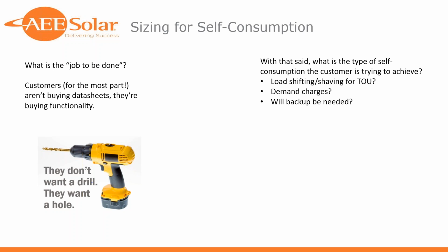And the last thing I threw in here, it's not a specific application on its own, but typically when we're talking about these solutions for residential customers, you've got to think, is backup going to be needed? It's going to add cost and complexity on the BOS side. You're going to have to think about things like critical load panels and islanding, but it's definitely a consideration, and can drive some different sizing as well. So I just wanted to put this out here as a frame of reference. Let's keep the customer's perspective in mind about what we're actually trying to achieve and how that is going to drive our sizing one way or the other.